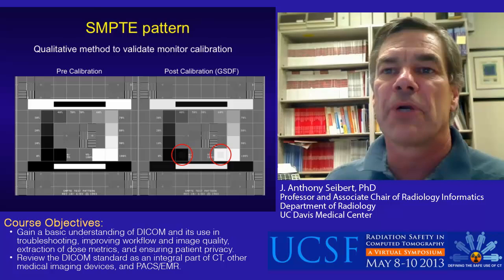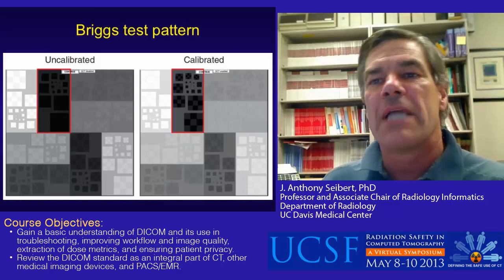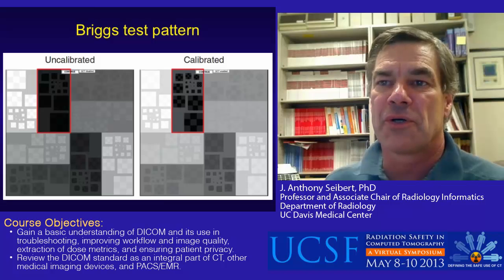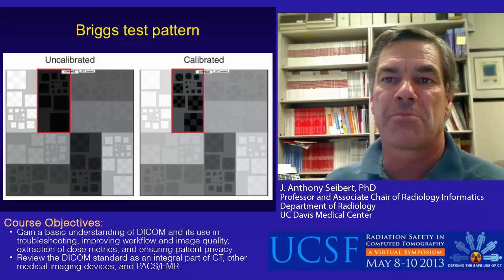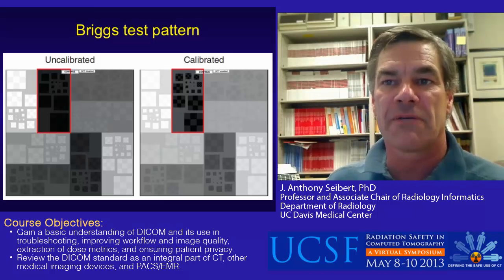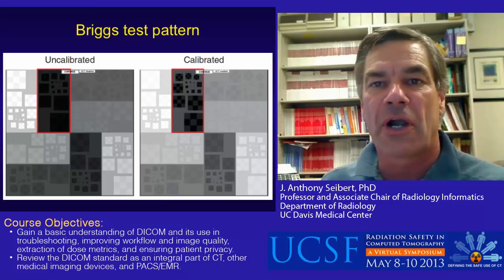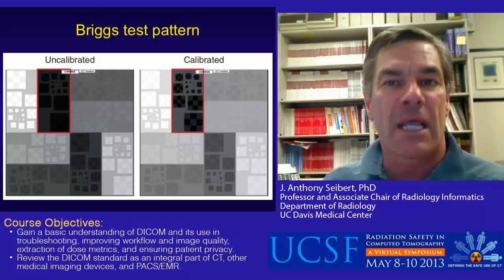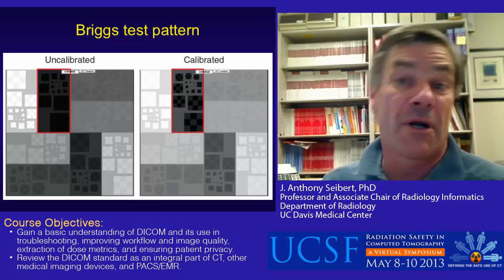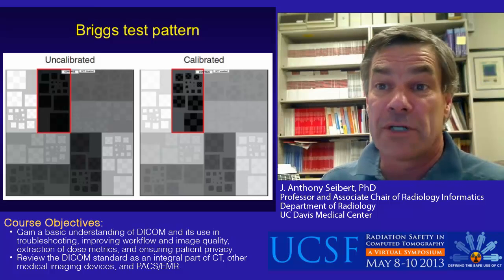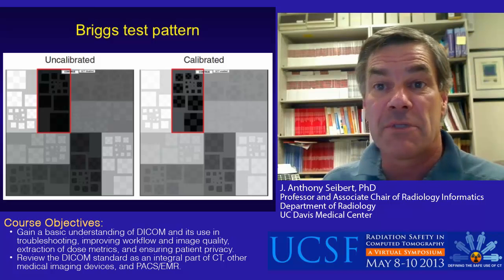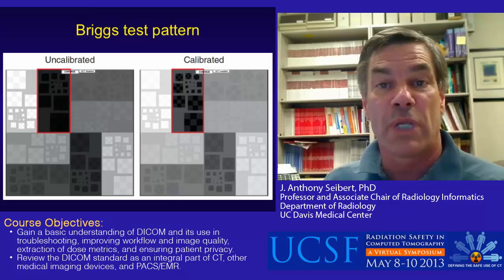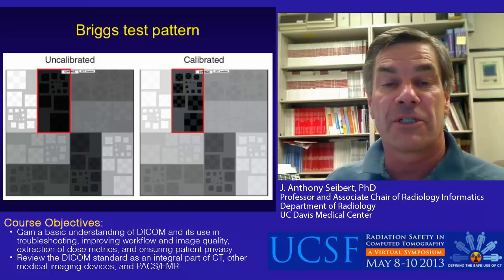Another test image called the Briggs pattern demonstrates the more pronounced impact of an uncalibrated monitor, particularly for displaying subtle differences in grayscale in the darker areas of the image, compared to the same image shown with a calibrated monitor on the right. Monitor calibration is a key aspect of the imaging system, as the image is only as good as its weakest link, which is often the monitor itself.